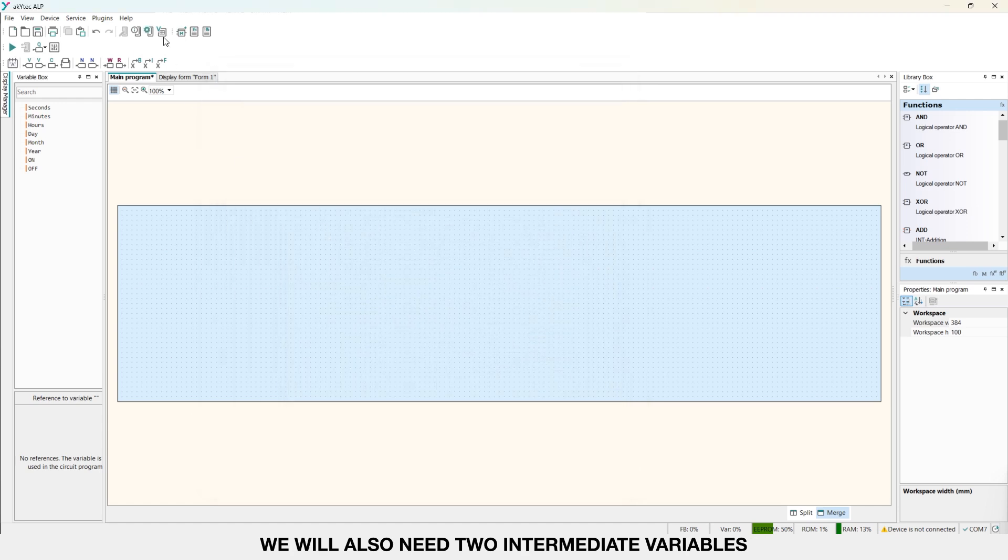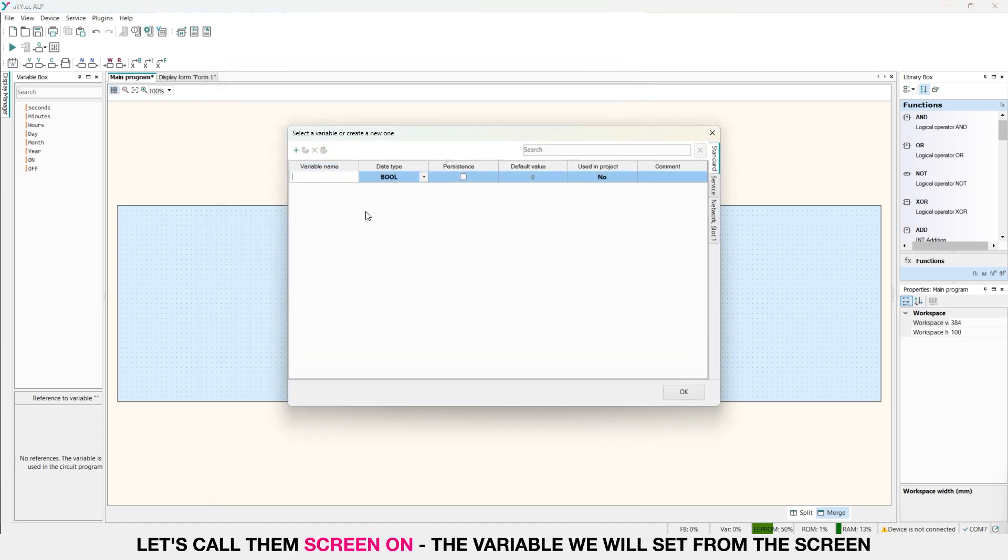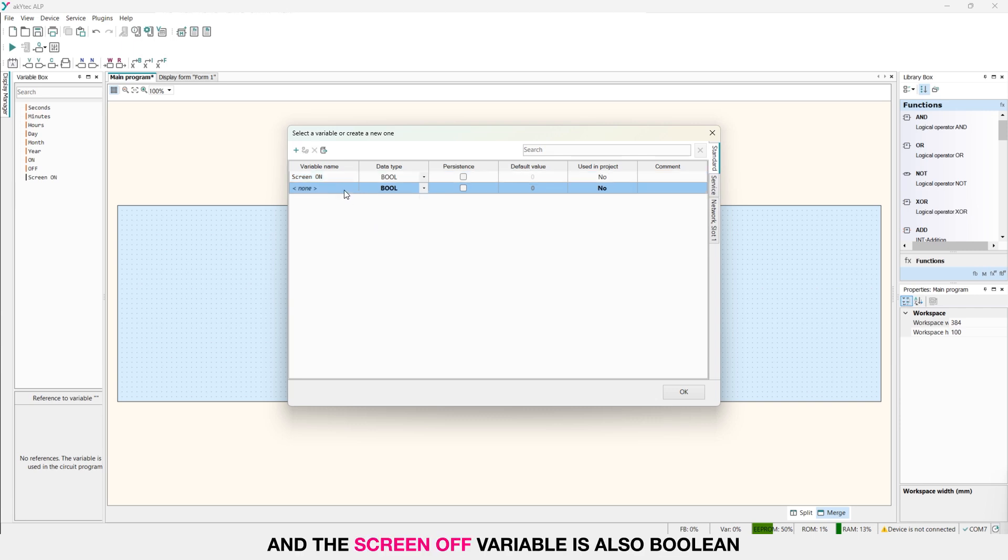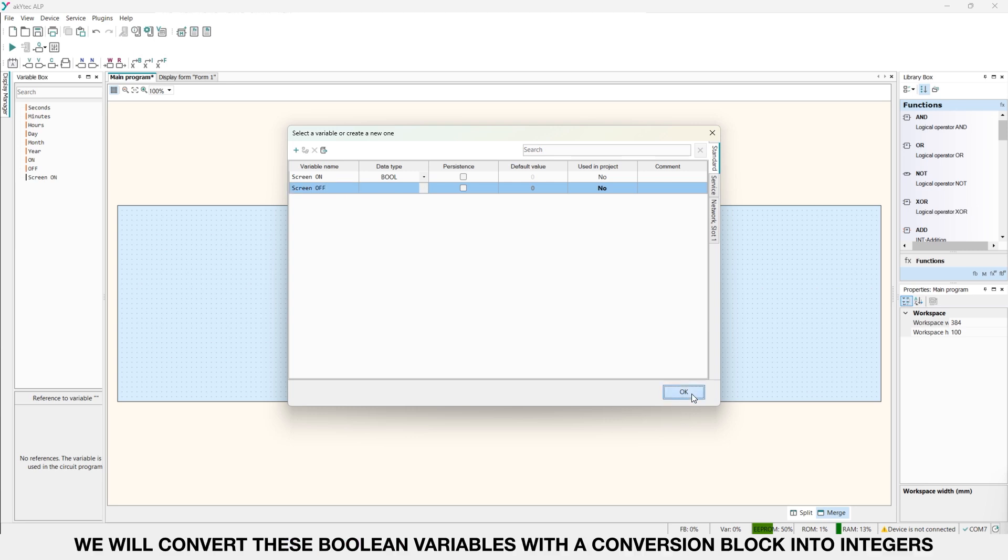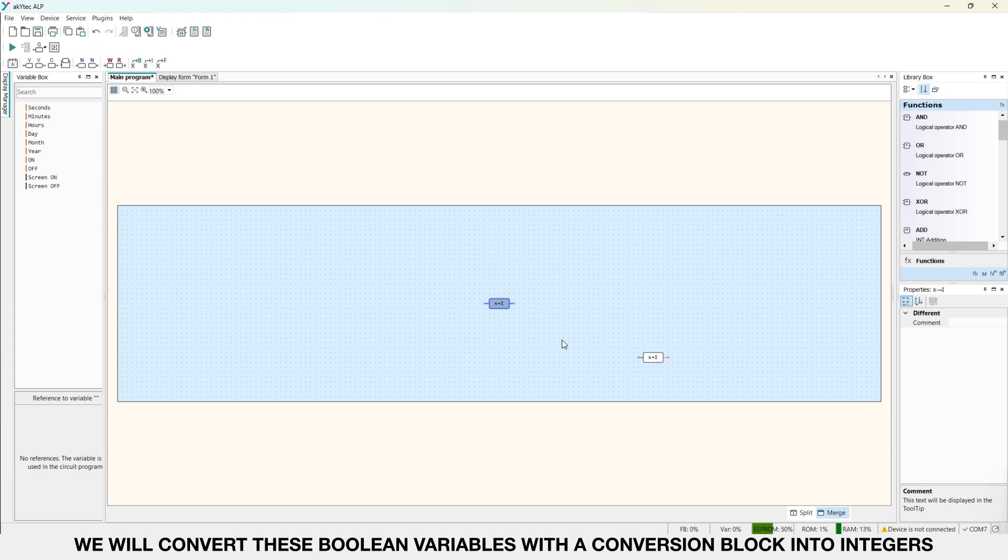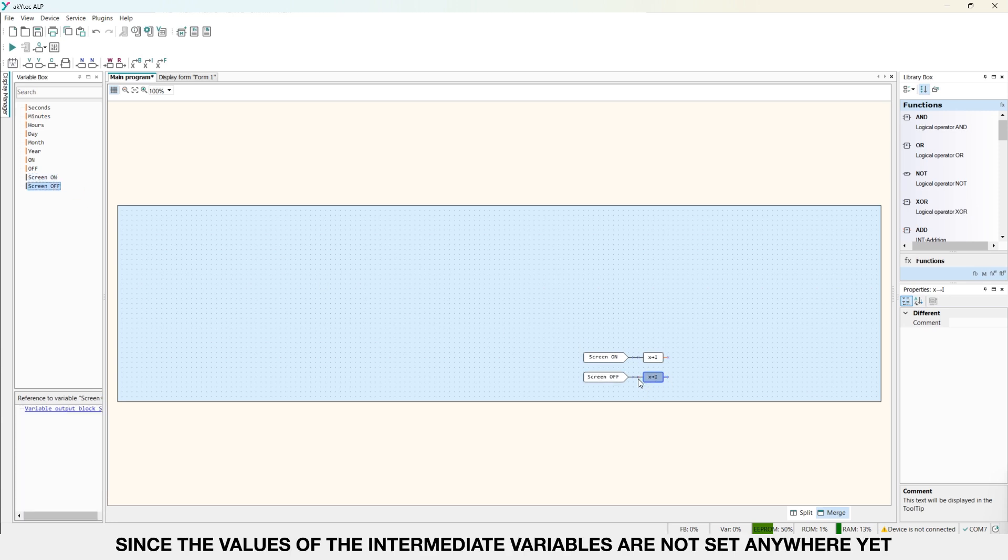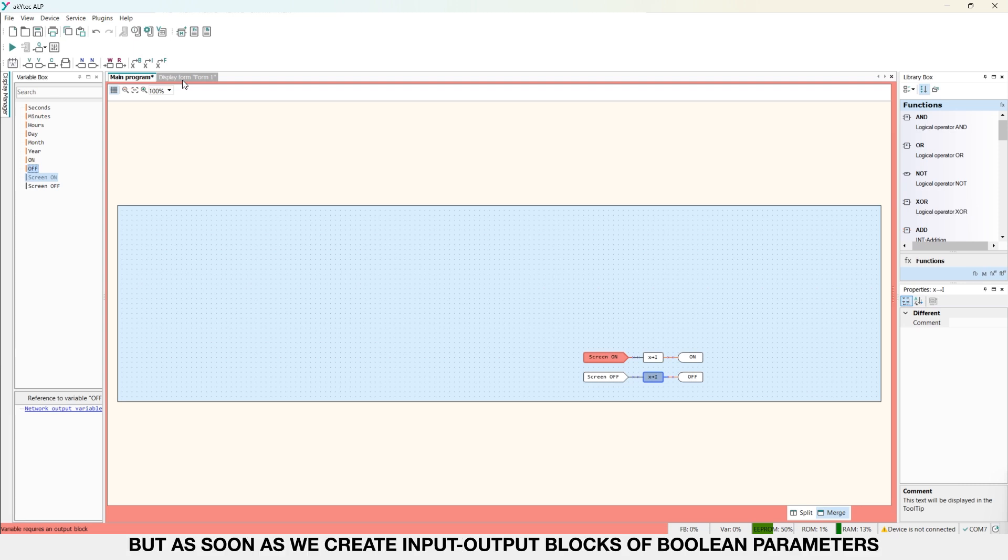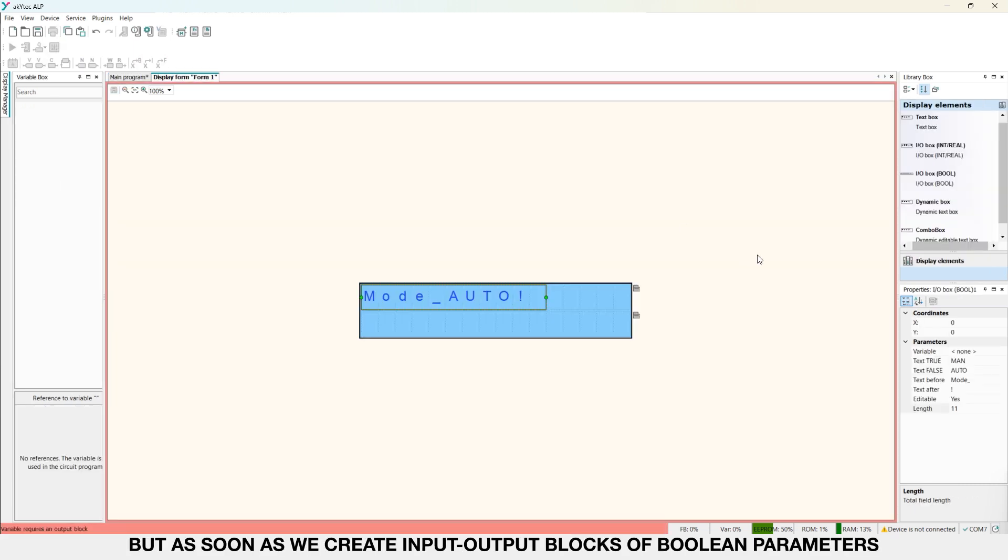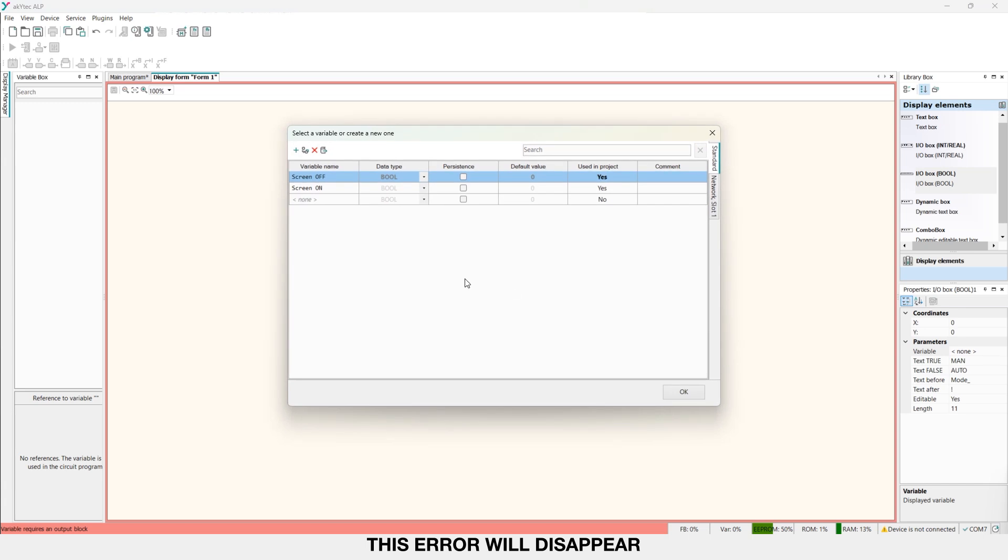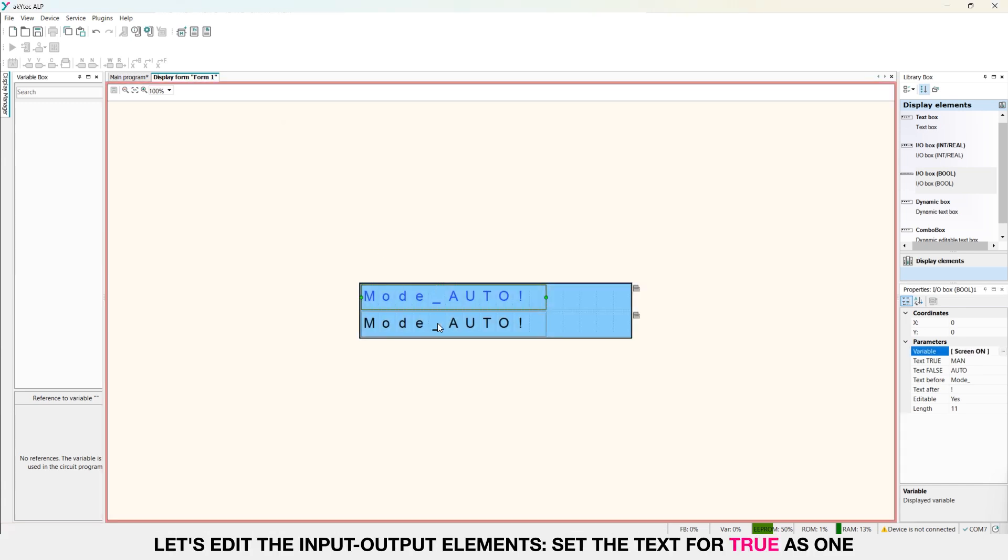We will also need two intermediate variables. Let's call them screen on, the variable we will set from the screen, which will be a boolean parameter, and the screen OFF variable, also boolean. We will convert these boolean variables with a conversion block into integers. And we write the conversion result into the network variables. Since the values of the intermediate variables are not set anywhere yet, ArchitectALP shows us an error. But as soon as we create input output blocks of boolean parameters on the screen and bind the corresponding variables there, this error will disappear. Let's edit the input output elements.